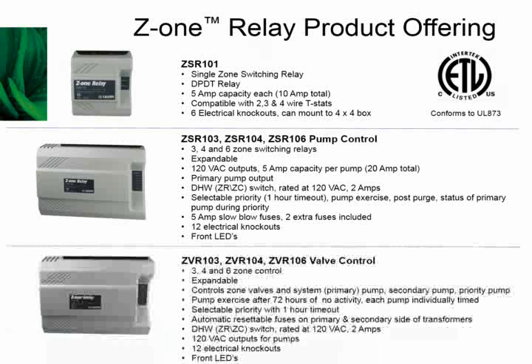Then the last member of the family here is the valve control. That comes in a 3, 4, and 6 control. Again, it's expandable. They communicate with each other. There's no real limit on how many you put together. It will control your zone valves, and also it can control a system pump, what we call a system pump, which could be your primary pump, a secondary pump, and a priority pump. So it gives you a lot of flexibility.